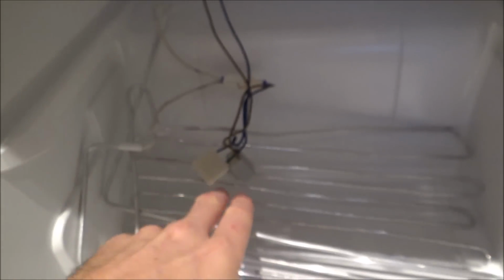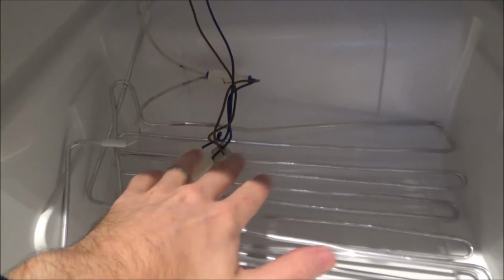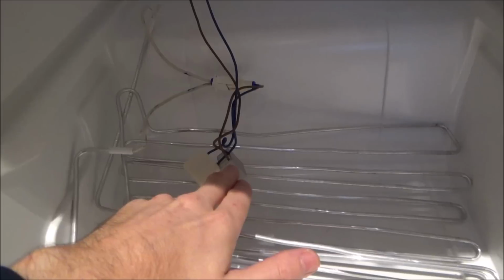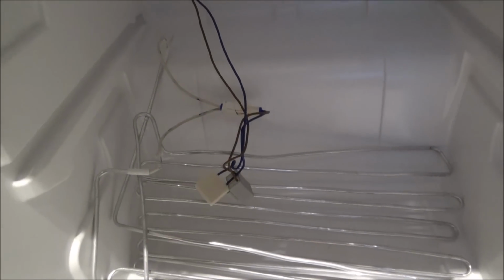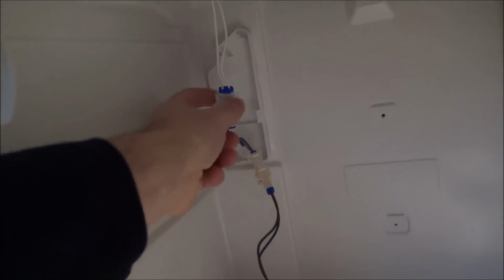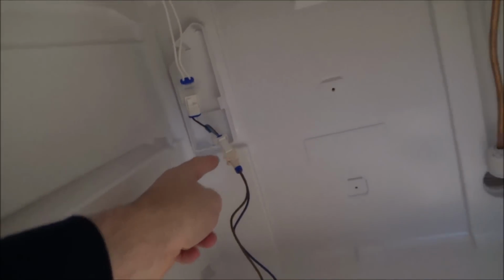Normally these are clipped to the actual pipework at the back, but I'm just leaving them here because they're only on the pipework to measure the temperature. Since I believe it has failed, it will throw up an error code. If you have a look now, this one is feeding the fan, the two white ones, and this one is feeding this setup here, going through here and then onto the heater element.